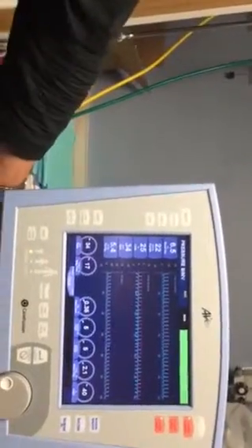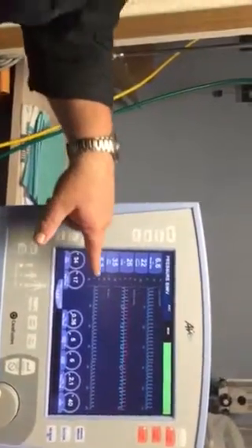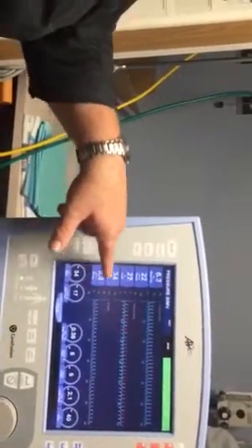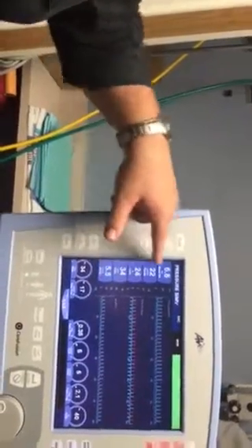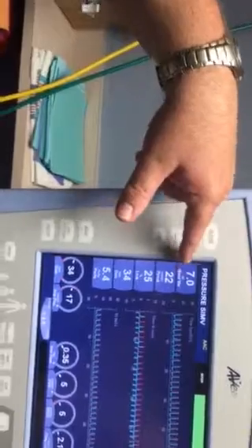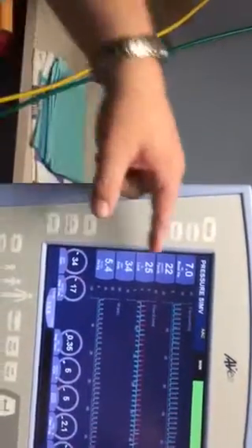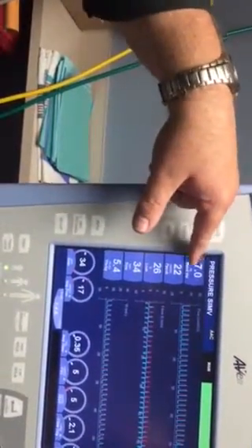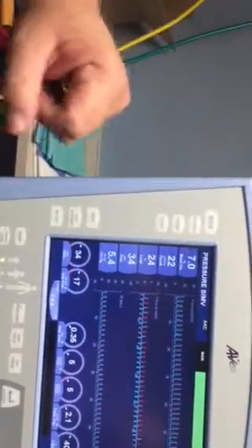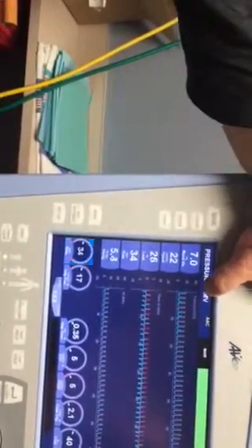Okay, so what I want to do is tell the ventilator that I want to keep in this range. And this range is being created by this VTE here. Okay, so it's always VTE. So I'm going to use this VTE as my target. All right, so I'm going to go into my mode screen, and there's volume guarantee.